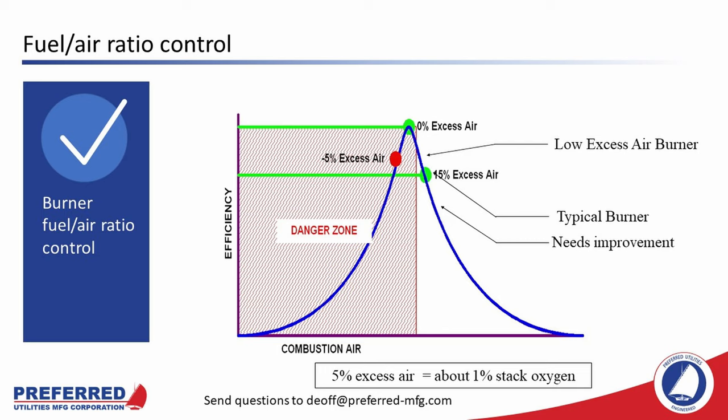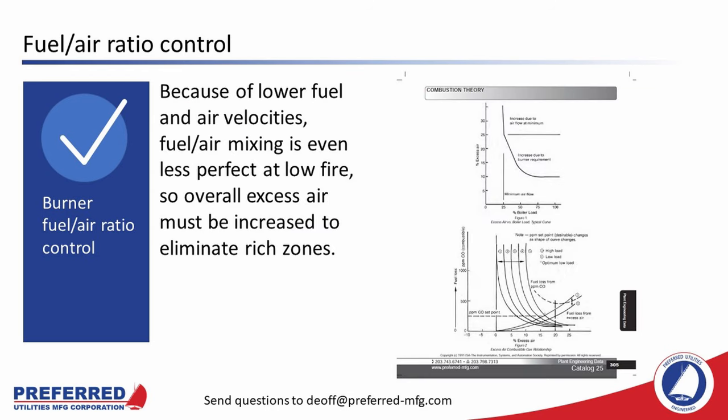This chart shows typical excess air levels and the danger zone if you burn too rich. Most burner manufacturers guarantee 15% excess air or 3% stack oxygen. Preferred burners will burn more efficiently — down to about 10% excess air or 2% stack oxygen. But note these excess air levels are at high fire only. Because of lower fuel and air velocities, fuel-air mixing is even less perfect at low fire, so overall excess air must be increased to eliminate rich zones. The diagrams in Preferred's catalog 25 show that excess air increases at lower firing rates — how much really depends on the burner.